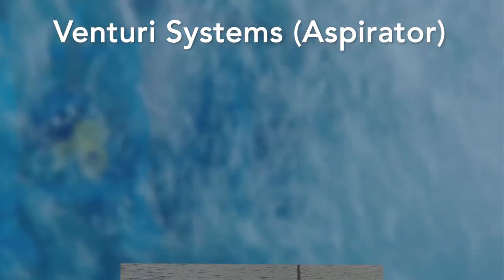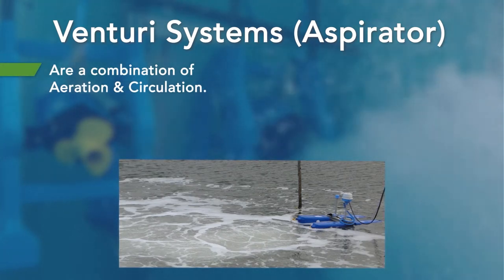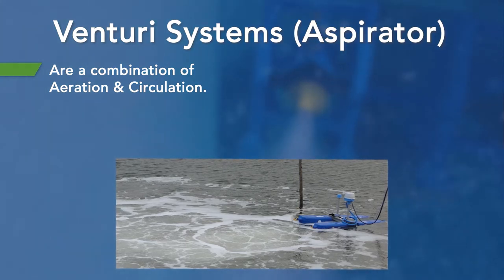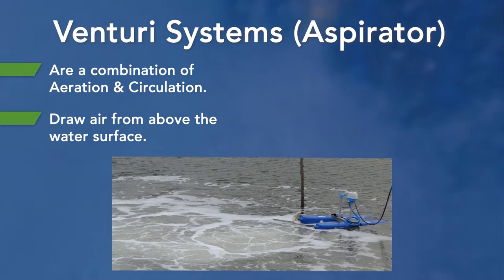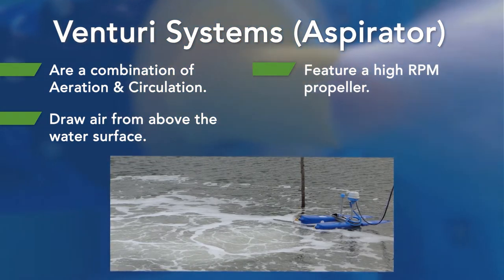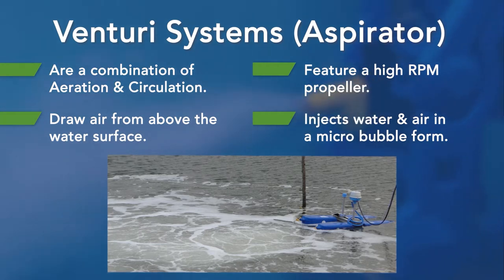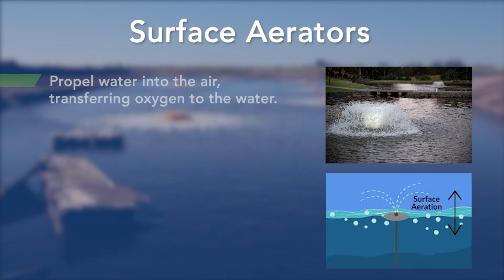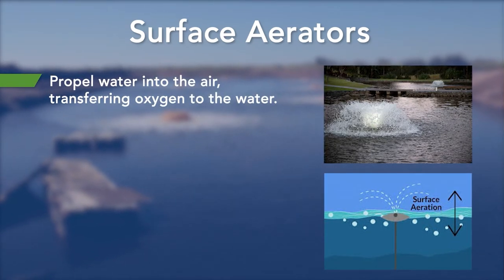Venturi systems utilize a combination of aeration and circulation, making them some of the most effective systems that introduce crucial oxygen at higher transfer rates. Venturi systems draw air from above the water surface and have a high RPM propeller that creates a negative pressure in a chamber, allowing injection of water and air in micro-bubble form. Surface aerators propel water into the air via a mechanical device so that the two elements come into contact and transfer oxygen from the air to the water.